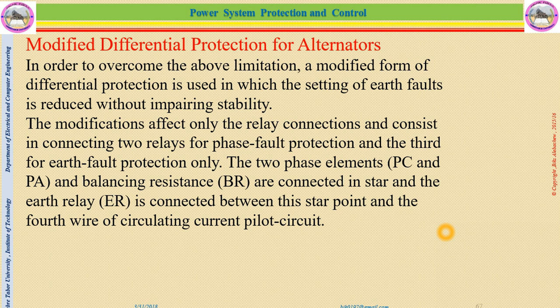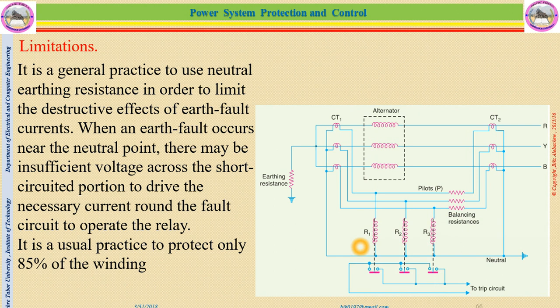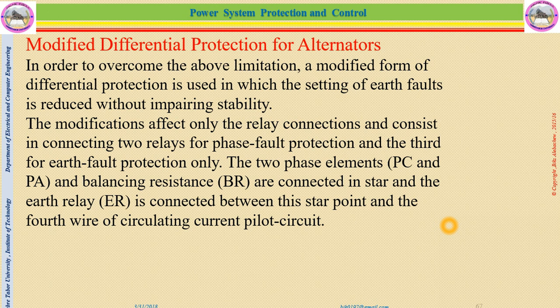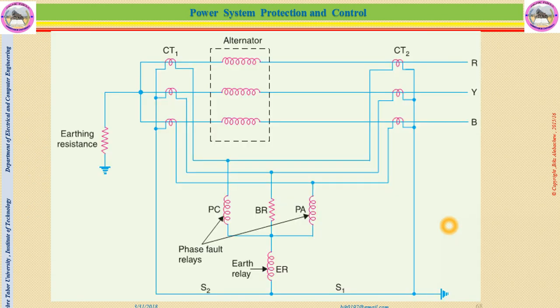In the previous one, we have independent relay coils for each phase, but for this modified one, there are two phase relays and one earth relay. There are three relays: two phase elements PC and PA, and balancing resistance BR, are connected in star, and the relay ER is connected between the star point and the fourth wire of the current pilot wire circuit. You can see this one.